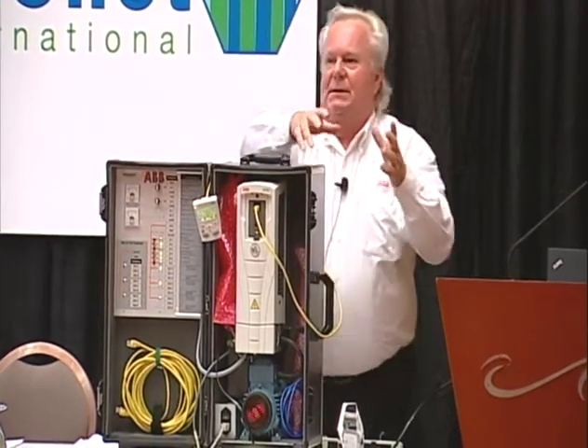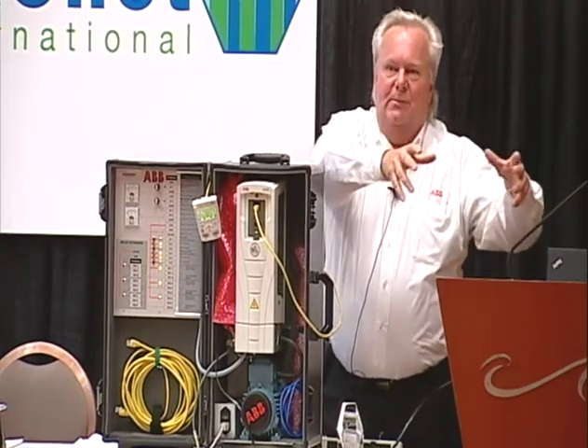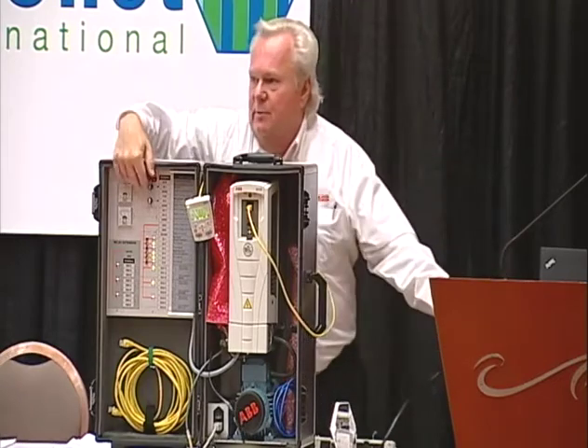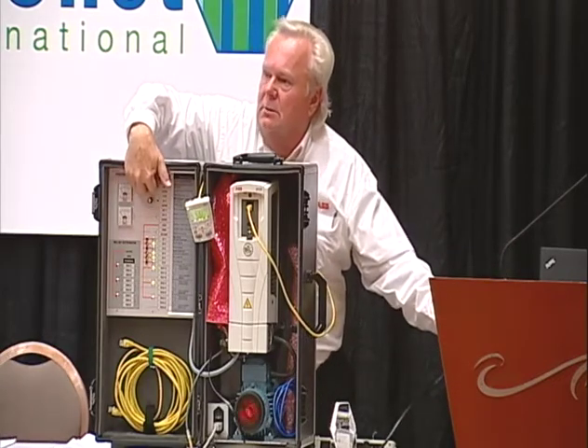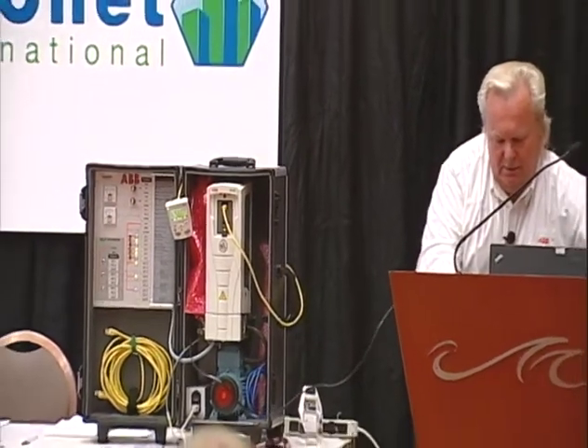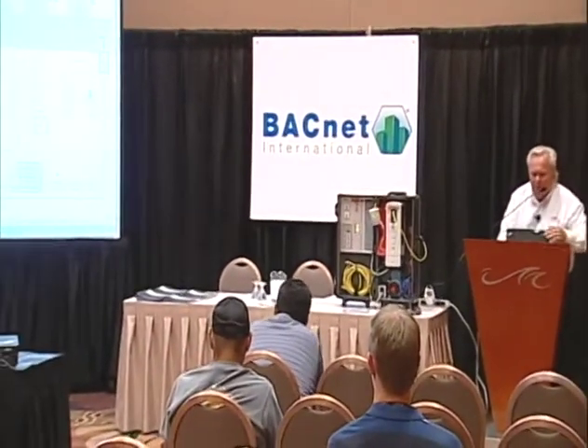So to me, DDC is not direct digital control, it's distributive digital control. You put the brains for the application as close to the application as you can. So this is the same way, you know, pick a name, the Delta control systems work. If they lose communications with the front end, they keep running their application there locally, right? Everybody with me? So I got standalone control, designed properly in my estimation. Now when I get communications back, when I reestablish, I find the cut wire and fix it, now I can go run night setback, and now I'll just run at a constant speed, whatever speed I want all night long.